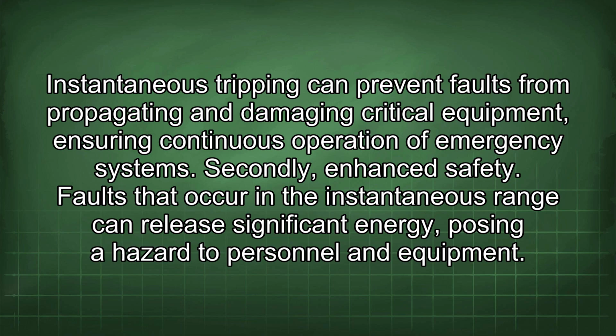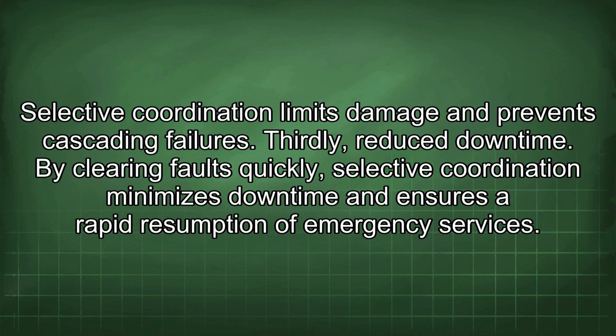Secondly, enhanced safety. Faults that occur in the instantaneous range can release significant energy, posing a hazard to personnel and equipment. Selective coordination limits damage and prevents cascading failures. Thirdly, reduced downtime. By clearing faults quickly, selective coordination minimizes downtime and ensures a rapid resumption of emergency services.